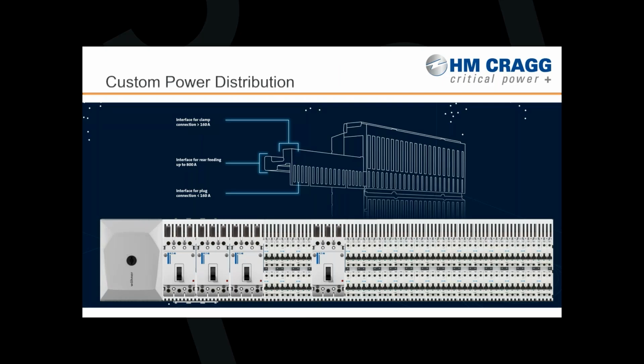This is a bit of an eye chart, but it really shows the density with which we can build with this modular bus bar system and the ability to mount devices anywhere along the busway. The busway we're utilizing is 800 amps rated, AC or DC, and can accommodate large frame size molded case circuit breakers all the way down to DIN rail supplemental breakers in a higher density output.